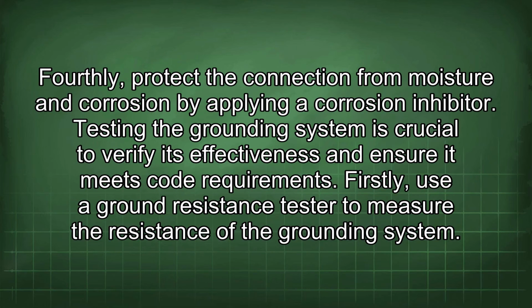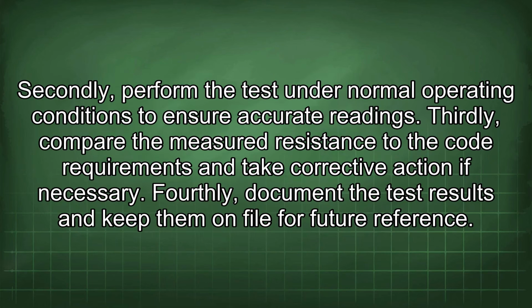Firstly, use a ground resistance tester to measure the resistance of the grounding system. Secondly, perform the test under normal operating conditions to ensure accurate readings. Thirdly, compare the measured resistance to the code requirements and take corrective action if necessary. Fourthly, document the test results and keep them on file for future reference.